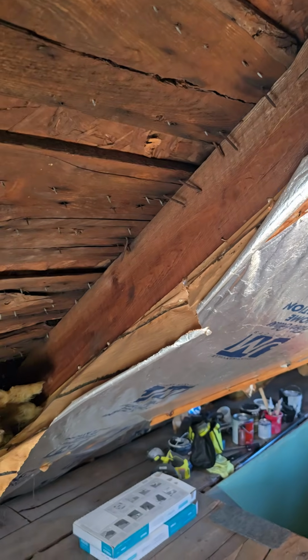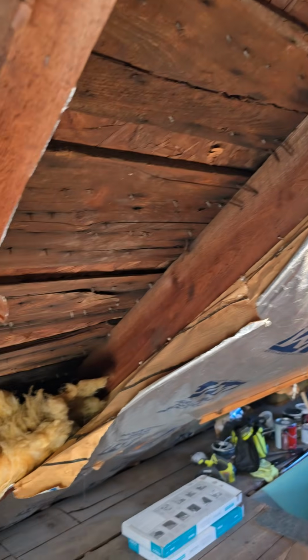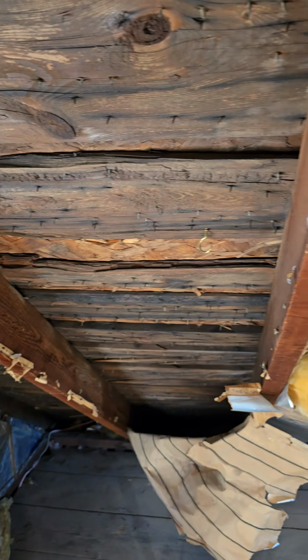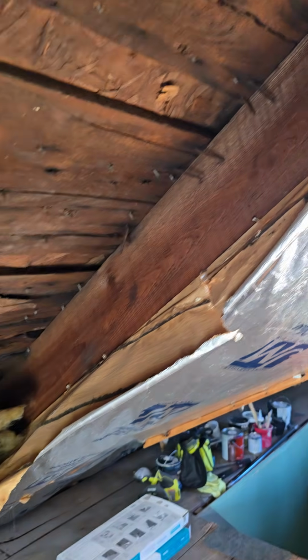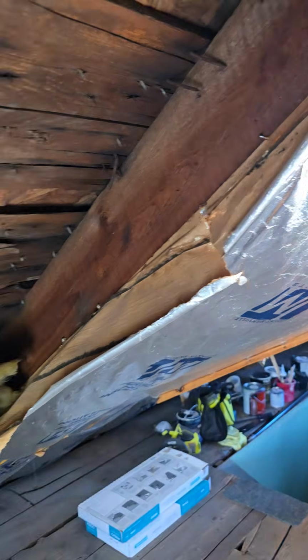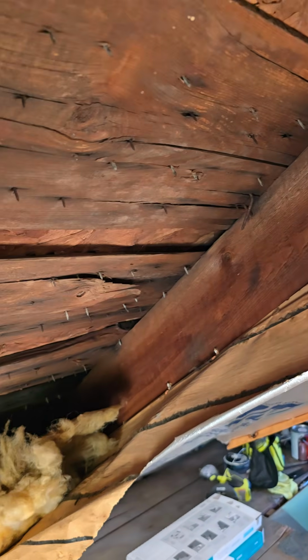So a couple of things. We're missing insulation, so we're definitely having a big issue as far as energy conservation and losing heat in this house. But the other thing is because they insulated the roof, there's no ridge vent and there's no soffit vents. So when that happens, we are having stagnant air behind all this insulation. So we most likely have mold everywhere.